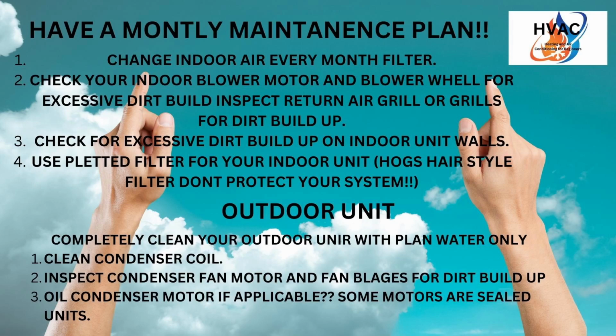These are just maintenance procedures. Another thing: those cheap hog hair filters you get from Walmart or Home Depot—if you hold one up to the light and can see through it, it does you no justice. That's just trash. You get 10% protection at best; the rest of that dirt just goes right through it. You're not protecting anything—you're throwing three or four dollars away every month for nothing, and still causing your system poor maintenance.